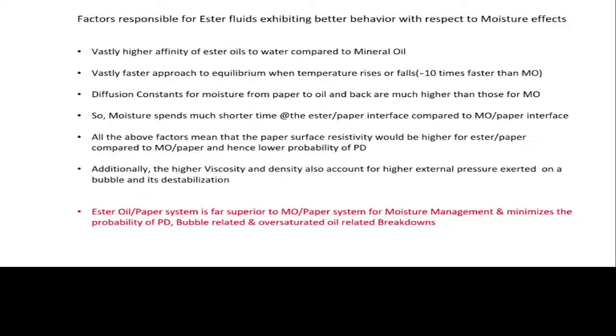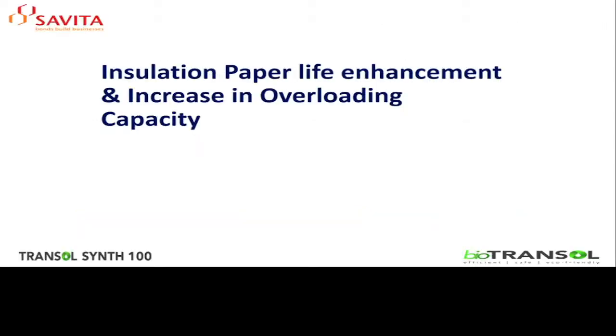Okay. Now the study on bubble formation at different moisture contents in oil immersed cardboards in natural ester oil. This is a comparison again for bubble formation. All that points to a very favorable moisture dynamics for the case of ester oils. And the bottom line of the presentation is that the ester oil paper system is far superior to mineral oil paper system for moisture management, and it minimizes the probability of partial discharge, minimizes the probability of bubble formation, and oversaturated oil. All these three instances are eliminated by using an ester oil.